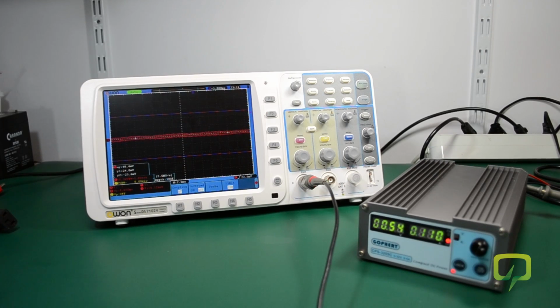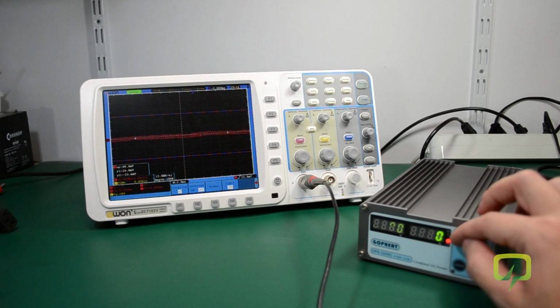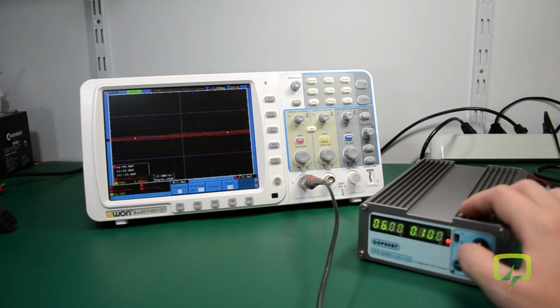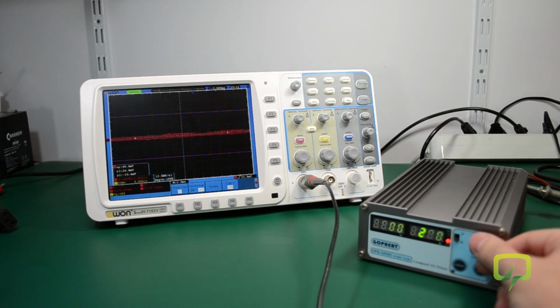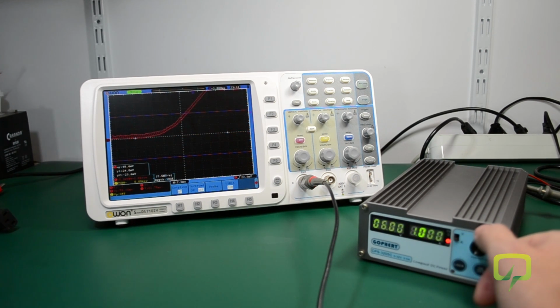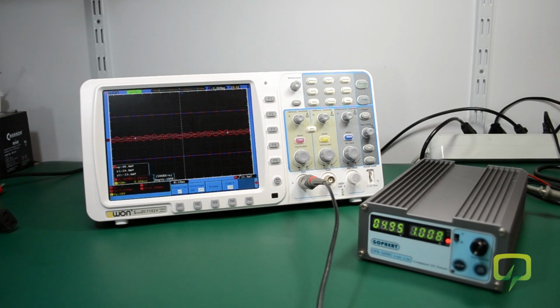So we got our first noise figure of approximately 7 millivolts, but that was with no load connected to the power supply, and that figure might change slightly if we increase the load on the output of the power supply. So for that I'm going to use a power resistor connected on the output terminals of the power supply. I'm going to slowly adjust the current limit and see if the noise figure increases. So for 500 milliamps we're still getting 7 to 8 millivolts peak to peak. Let's see for 1 amp. At 1 amp we're still getting 7 millivolts of peak to peak output noise.